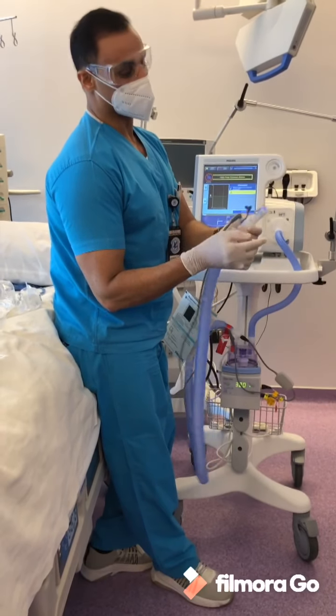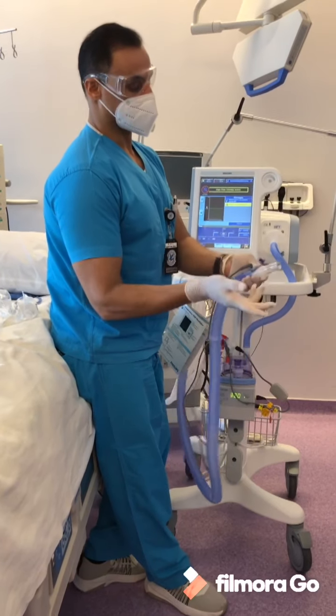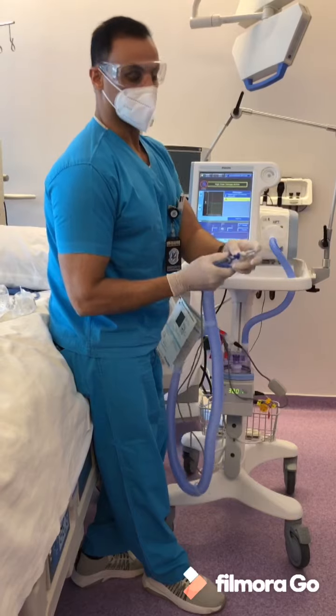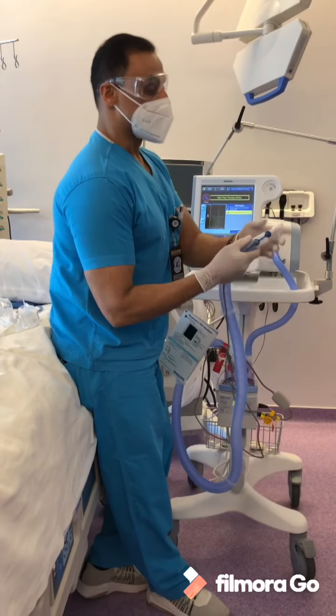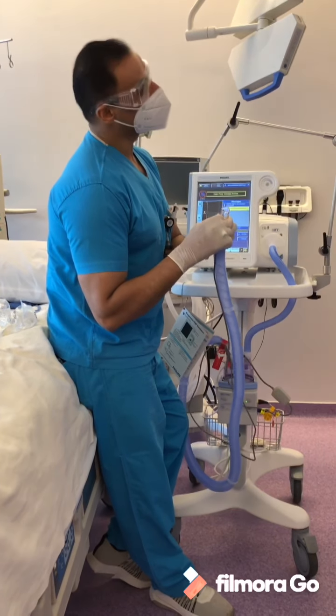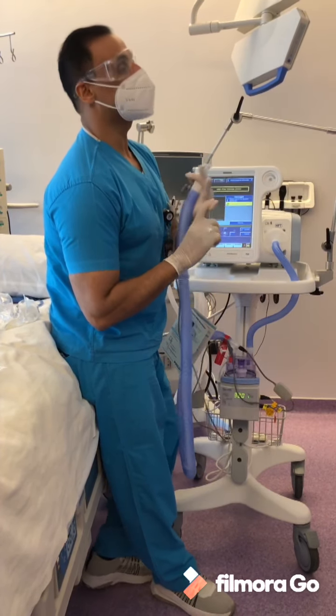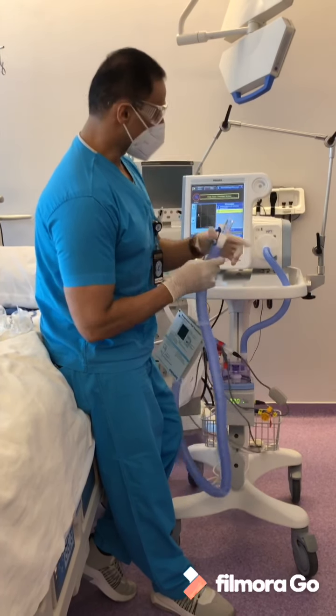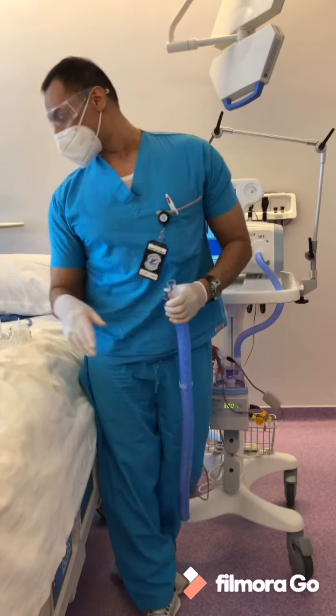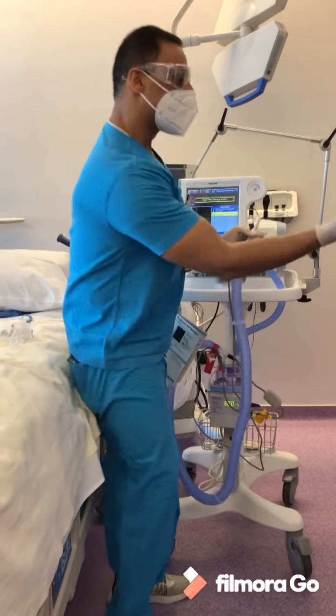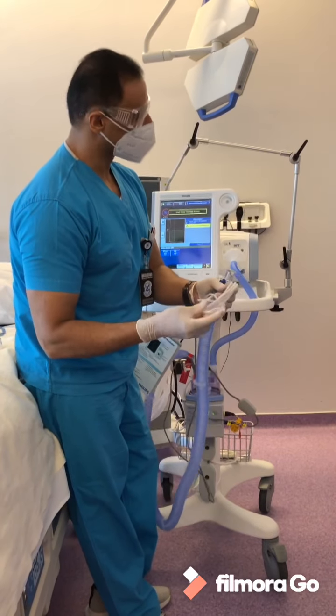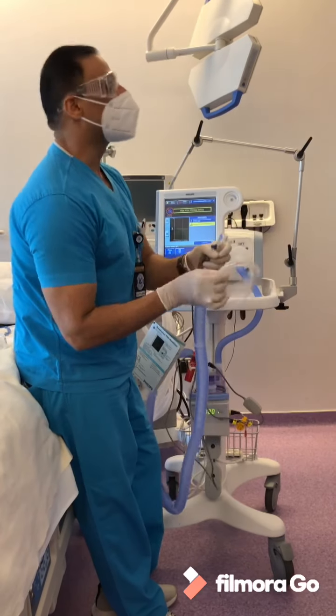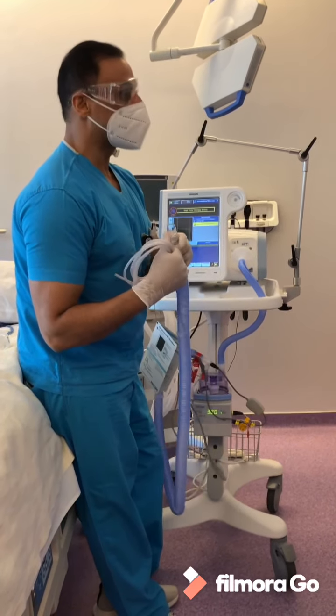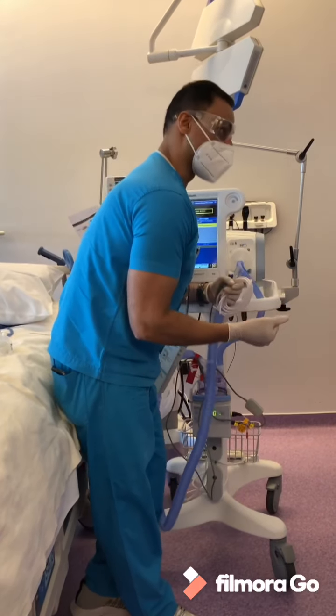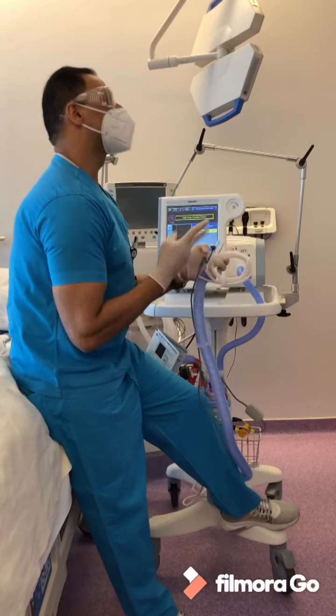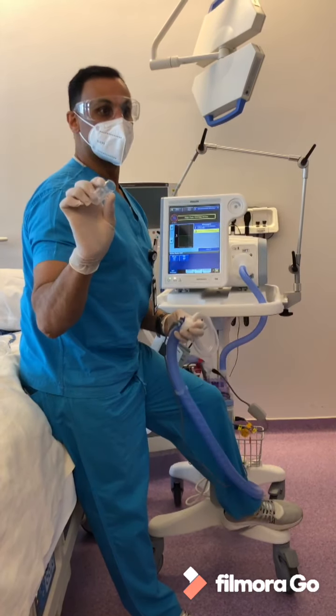So it's a universal size. Exhalation port. And then you need one more tubing. Why? To check your measurements: how much tidal volume he's taking, how much minute ventilation, by connecting here. Some of them also come in line. There are two types of this high flow tubing actually. I saw one that comes with these and one without it. If you see a tubing that doesn't have that one, then you need to open a BiPAP circuit, or you can waste the tubing by cutting this piece only. So it's up to you.